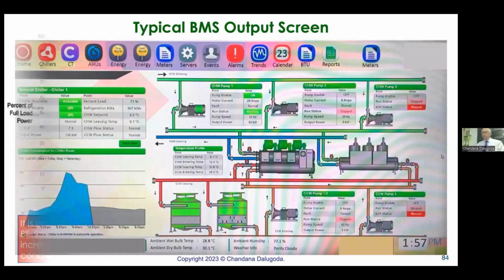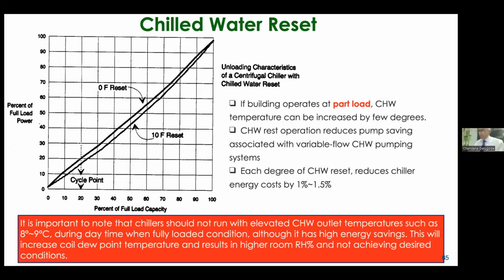Chill water reset. What is chill water reset? As you know, the chill water produced by the chiller is at 7 degrees C leaving and incoming 12. Actually, it is 6.6 and 12.2, but say 7 and 12. But if you generate chill water at 7 degrees C throughout the day, it is an energy killing.